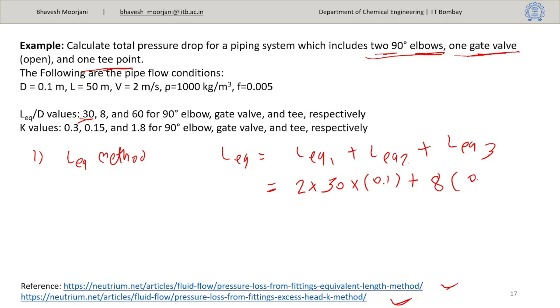So if you compute, this will come around somewhere 12.8. So the equivalent pipe length because of this fitting is 12.8. So the total length of your system will be L total, which is L actual plus L equivalent. L actual we have is 50 meter, so 50 plus 12.8, right? So this is 62.8 meter.